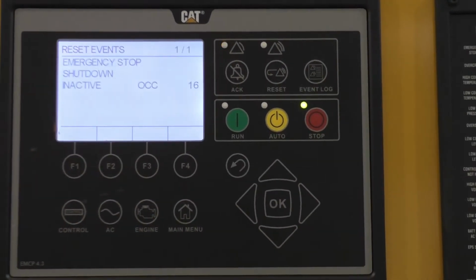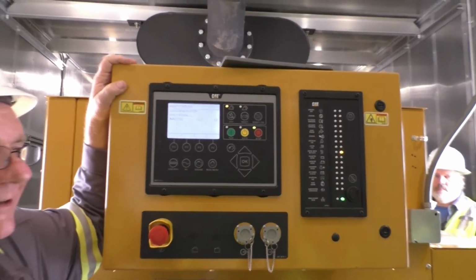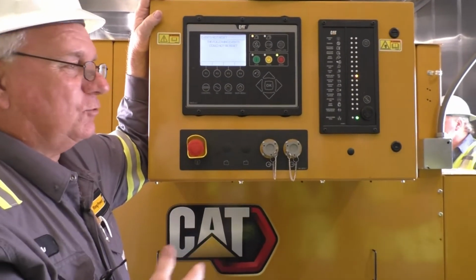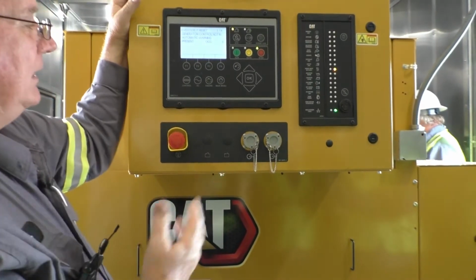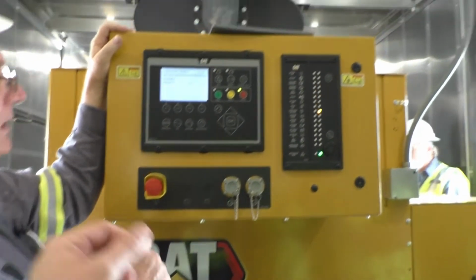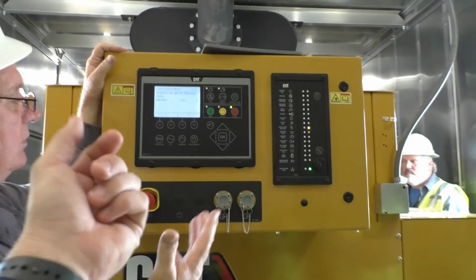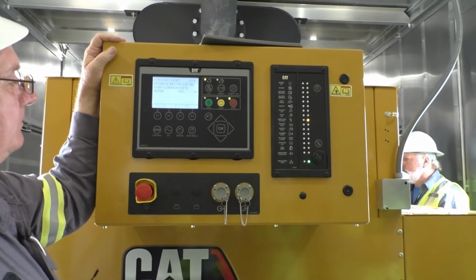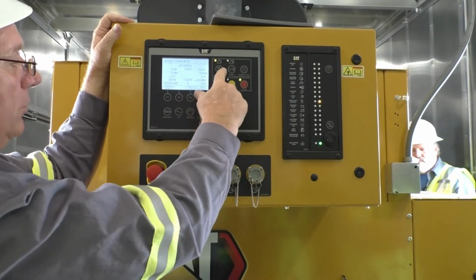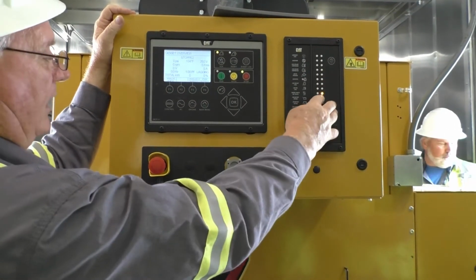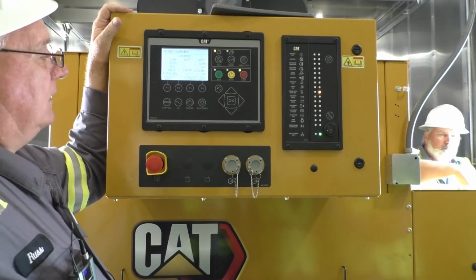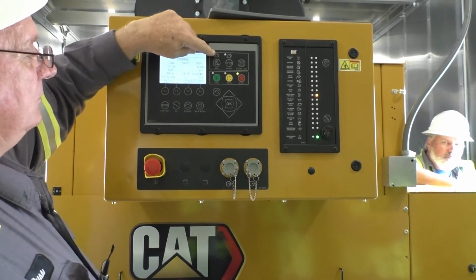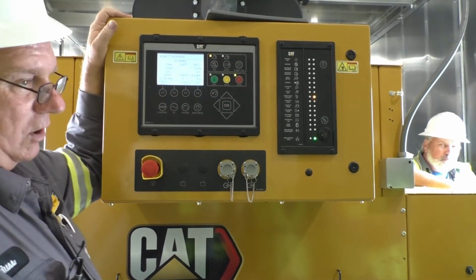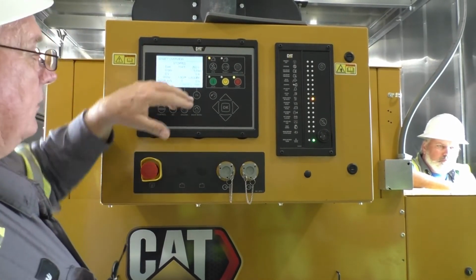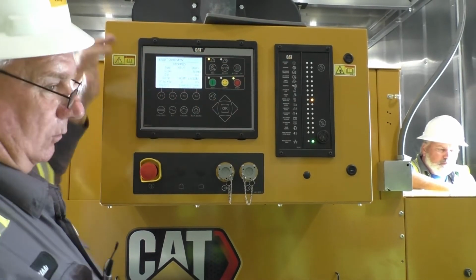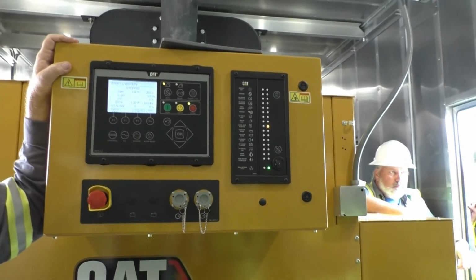Then I hate this part. It's got to go through everything it did and didn't do before it lets you go back to a regular screen. Takes a few seconds. It is what it is. It's telling you things that won't reset because they're active. The maintenance interval, which shouldn't even be on, I'll turn that off. And then it'll pop back to the screen you were on. You can acknowledge we still have a not in auto. We still have the breaker open, so you're going to have that light unless all events are gone. But just remember, if you have any sort of a red shutdown, it has to be in stop to reset or it won't reset. But it will walk you through that. And if you watch the screen, it'll tell you.